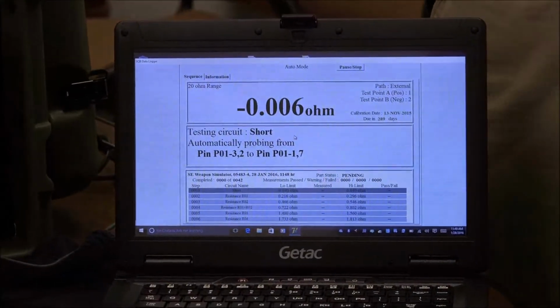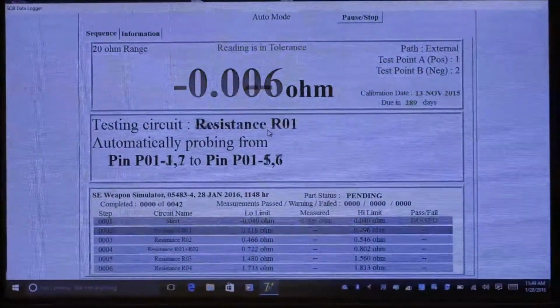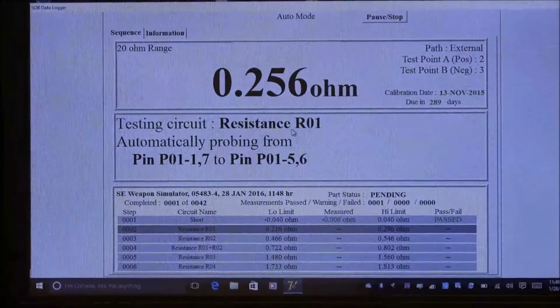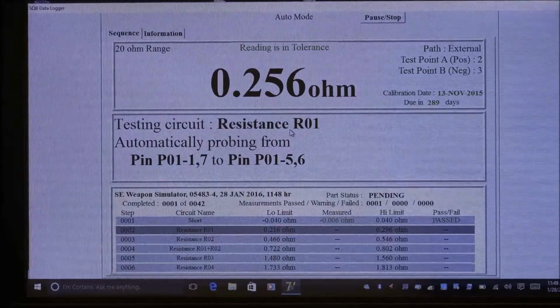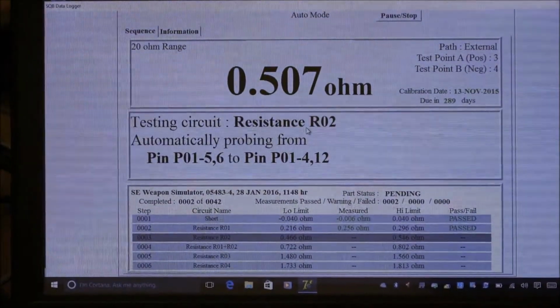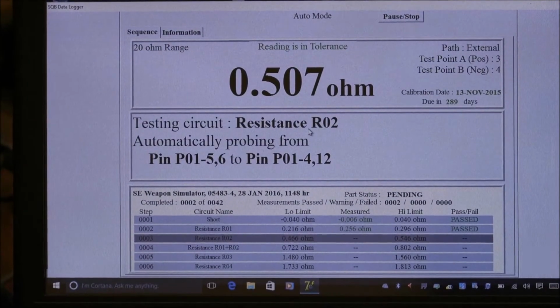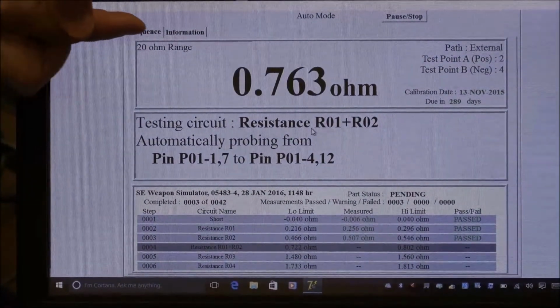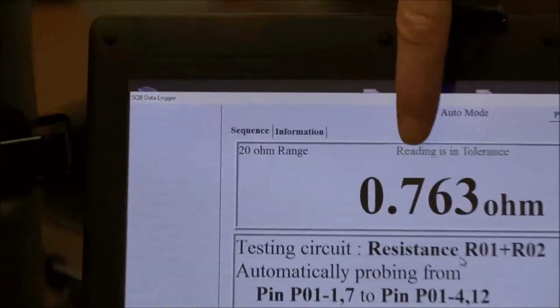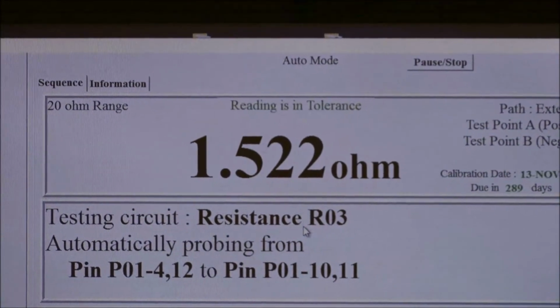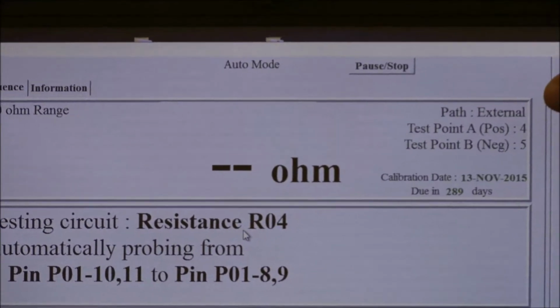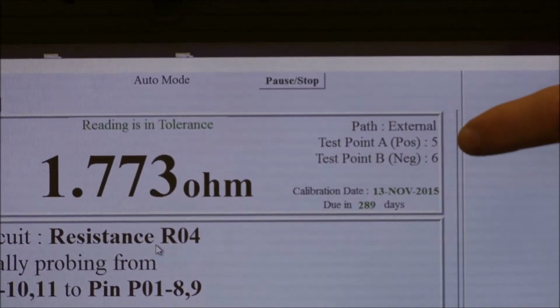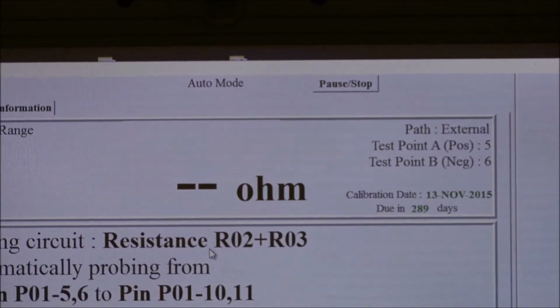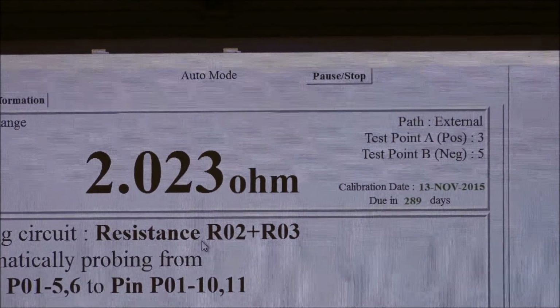If this system had the cable ID function, this is where it would do that verification measurement of each cable's resistance to validate whether it's correct. In this case, we don't have that function, so we've moved on to doing measurements. On the measurement screen, we see the unit or the range that the tester is being measured in, the value that's been measured, whether that value is presently passing or failing, whether it's internal, external circuit path, and what test points are A and B. The test point A is the positive side. For resistance tests, that's not important. But for voltage tests and diode tests, it is important.